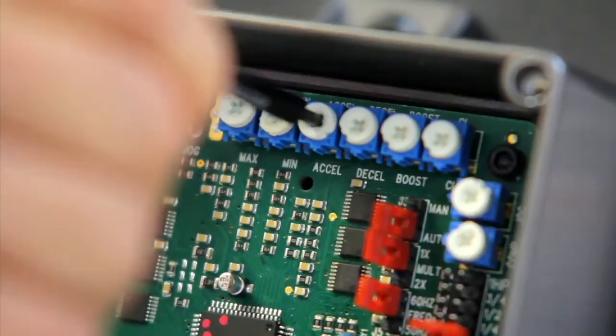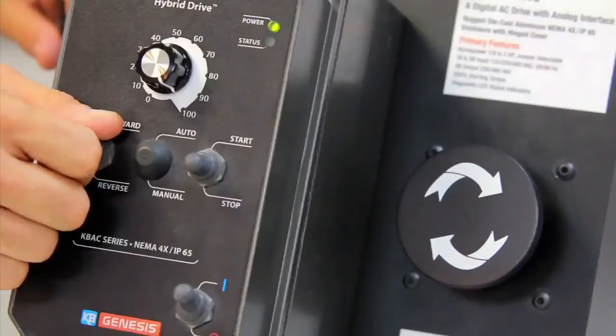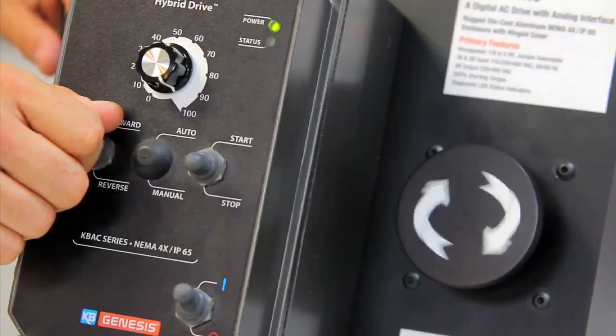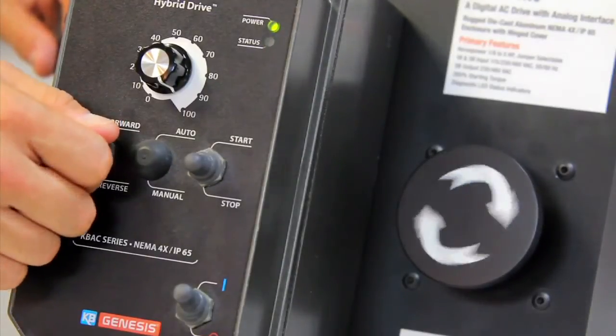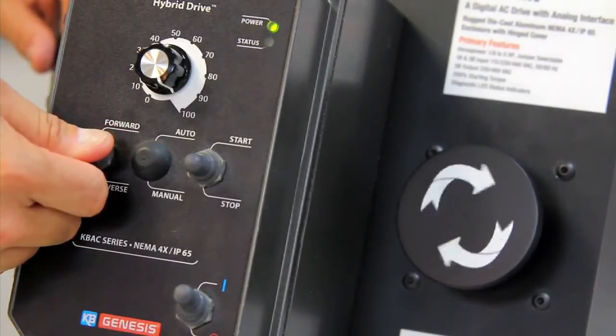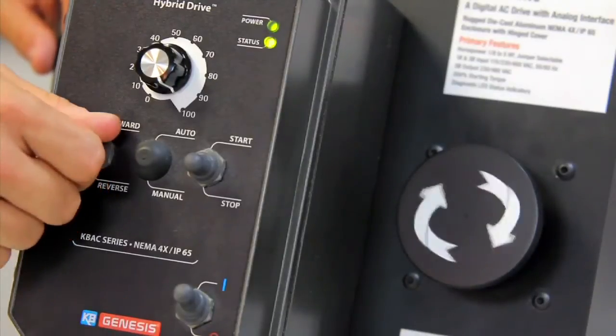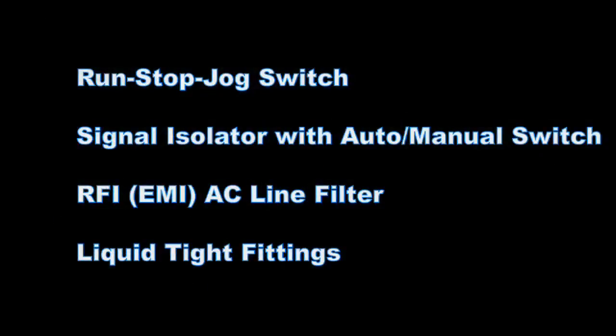Adjust both trim pots to the maximum position by turning them clockwise. The motor now operates with slow acceleration and slow deceleration. Please refer to the user-friendly manual included with the drive for additional adjustments. Other options include run, stop, jog switch, signal isolator with auto manual switch, RFI AC line filter, liquid tight fittings.